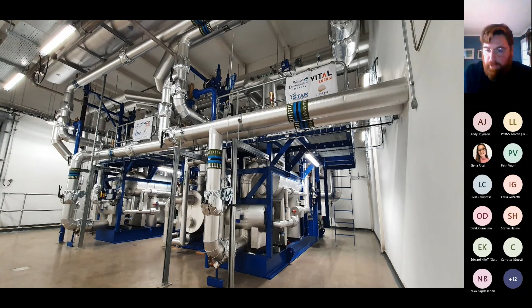Now what does this look like? I've given a little diagram here to help explain. Those heat pumps by Star Refrigeration are two 2.65 megawatt water source heat pumps. We also have two backup gas boilers at 7 megawatts each, to give us resilience and ensure we meet a peak demand of about 20 megawatts with the current system in the energy centre. It can achieve temperatures of up to 80 degrees if required.